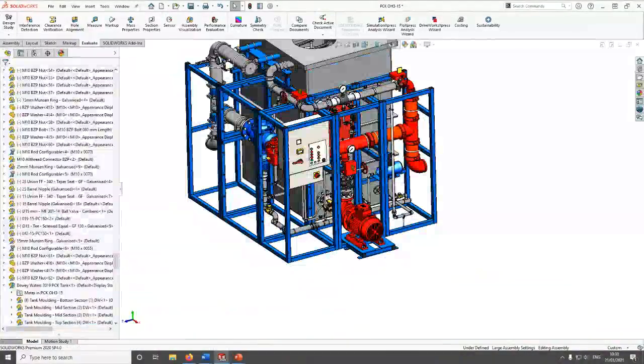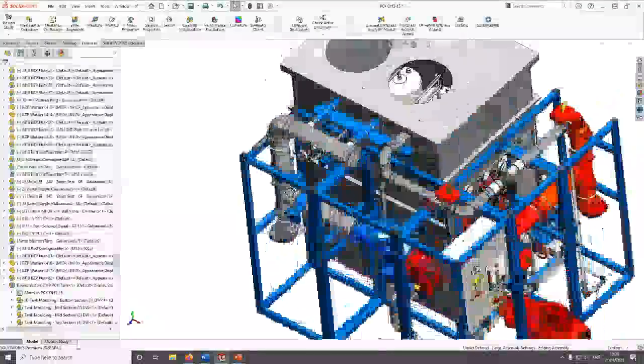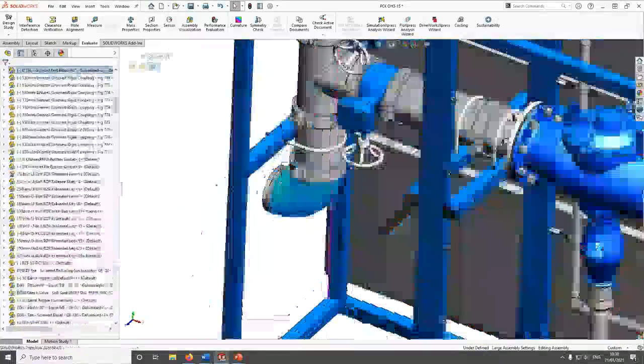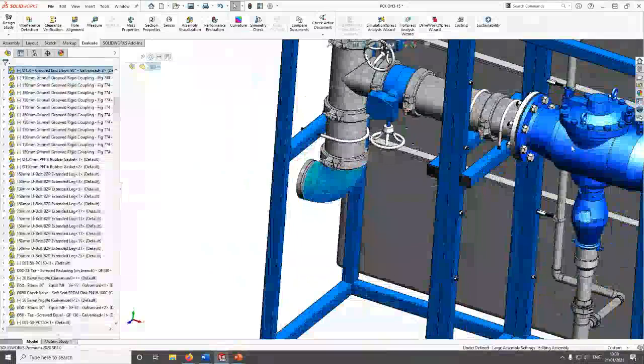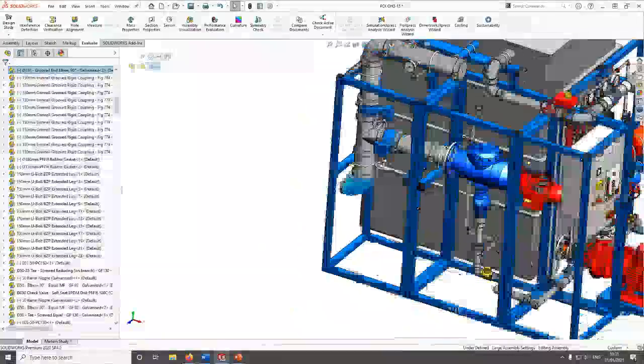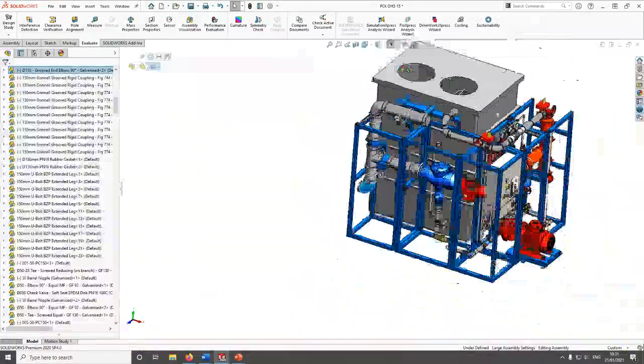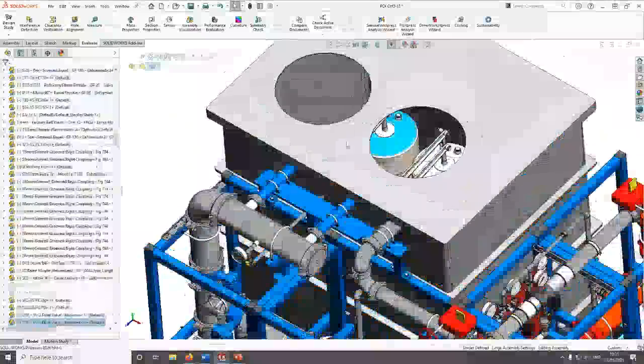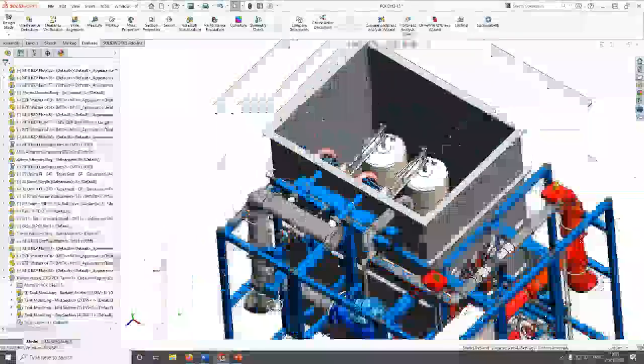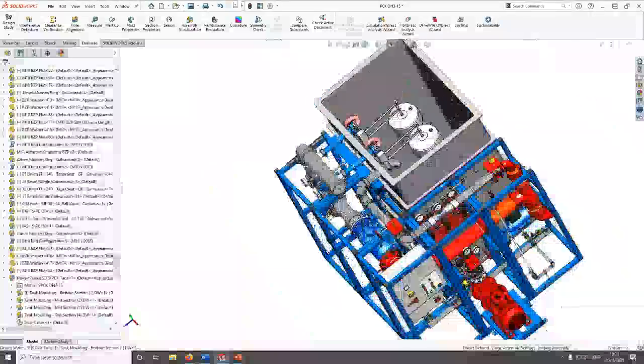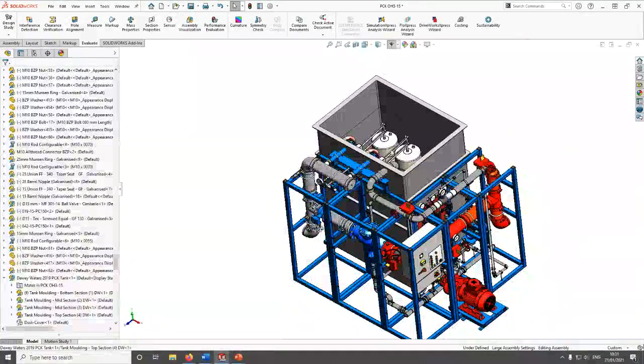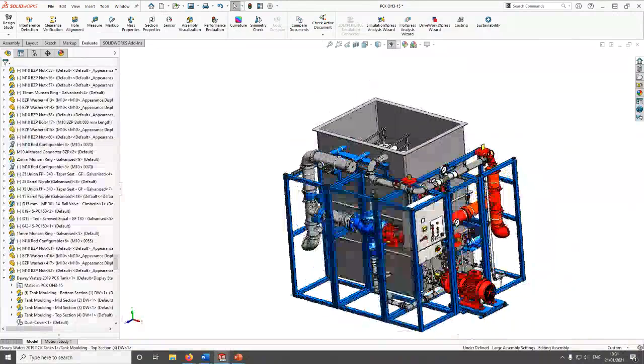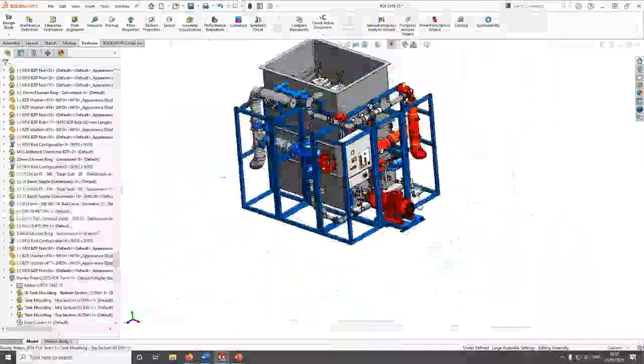Now, this tank is going to empty pretty quickly, of course. However, it is getting refilled from the town main. So the town main is coming through here. It's now not going through the AVC because water takes the path of least resistance. As the water level in our tank goes down, the float valves that you can see here, let me just hide the lid so you can see inside, are going to drop. That's going to mean that water is going to start to fill up the AVC to refill it. So can you see, hopefully, that as long as we're getting sufficient flow into this AVC, then our fire pump will be able to deliver the pressure required for the duration for an ordinary hazard system.